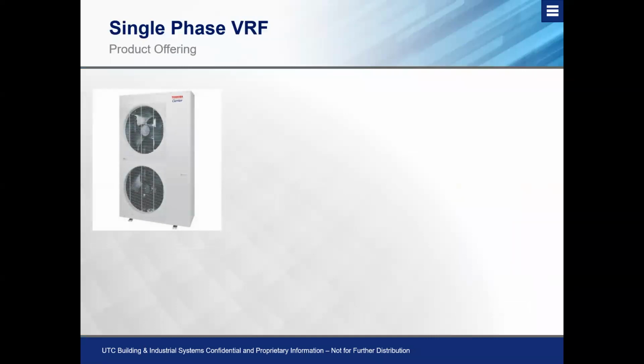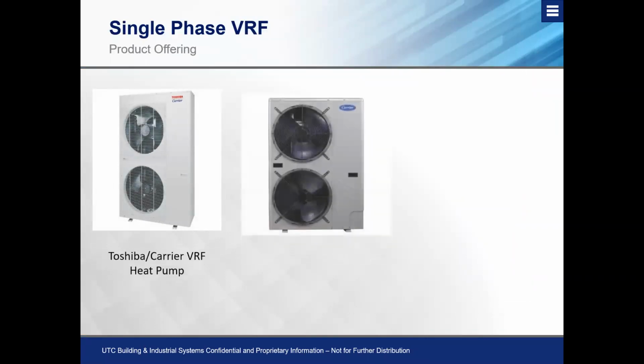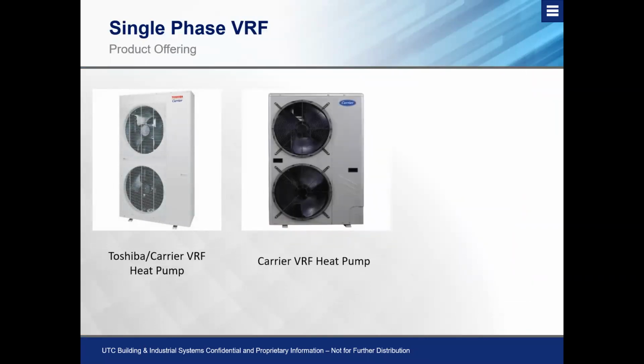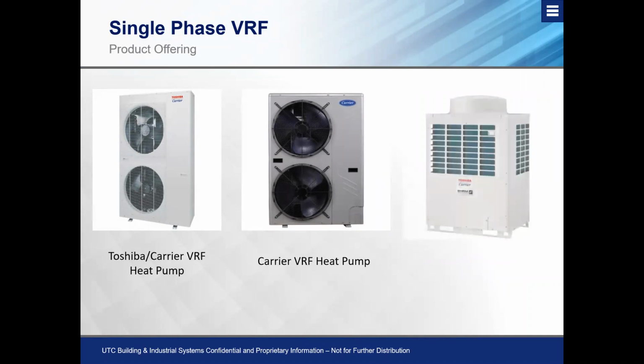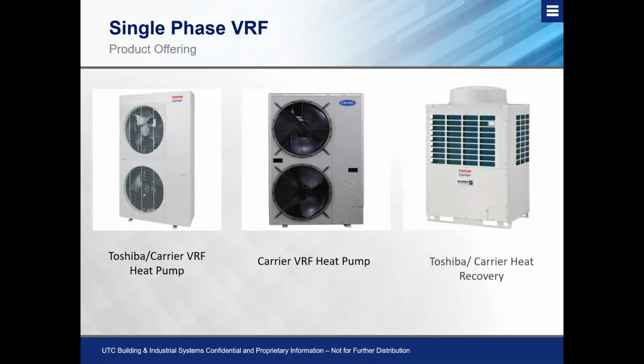So we have a Toshiba Carrier model. We have our straight Carrier single phase VRF heat pump. And then we have our Toshiba Carrier single phase heat recovery, which is a great application for light commercial, which does not have access to three-phase power, or larger residences looking for that simultaneous or that heat recovery capability.